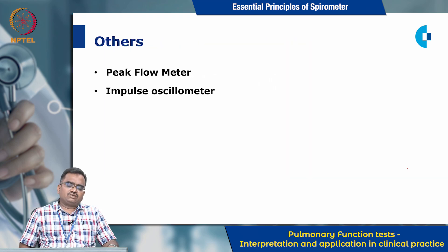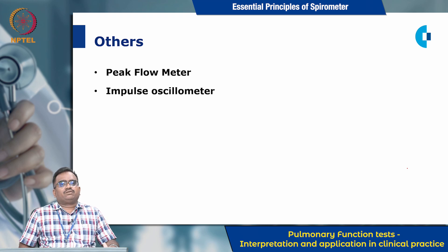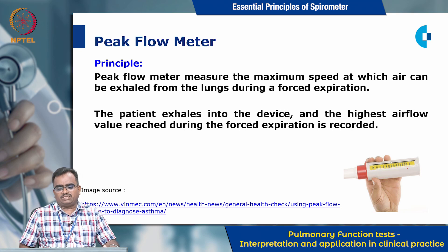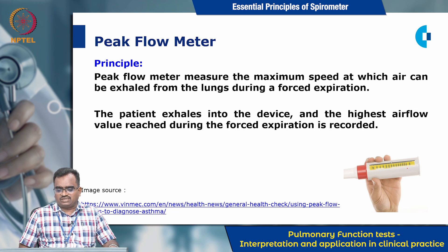Apart from spirometers, other devices used to measure pulmonary function include the peak flow meter and the impulse oscillometer. The peak flow meter works based on the principle of airflow rate — it measures the maximum speed at which air can be exhaled from the lungs during forced expiration. The patient exhales into the device and the highest airflow value reached during forced expiration is recorded.